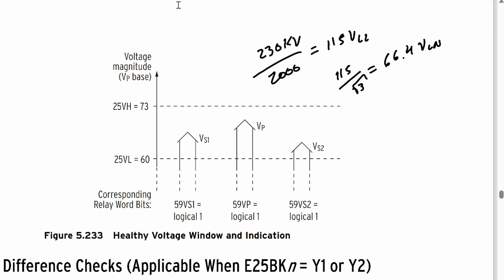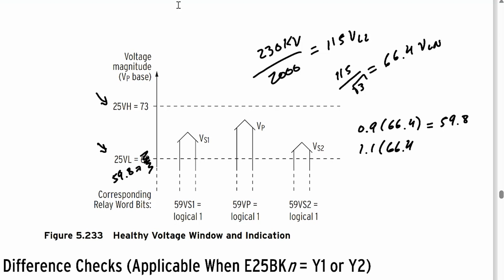So then we can set this band with these settings, 25VH and 25VL, to be plus or minus 10%. So we can say I'm going to set my lower end of that window to be 0.9 times 66.4. That gives me 59.8. So for our case, this is going to be 59.8. And I can set the top side of that band to be 10% above the nominal voltage. So 1.1 times 66.4 is 73.0. And that matches this. I'm just going to add the decimal point. So again, when we say that the line side voltage is healthy, we've defined that to be when the phase to neutral on the A phase is within 59.8 volts and 73 volts. That's plus or minus 10% of the nominal voltage. And we're going to do the same thing for the bus side voltage.